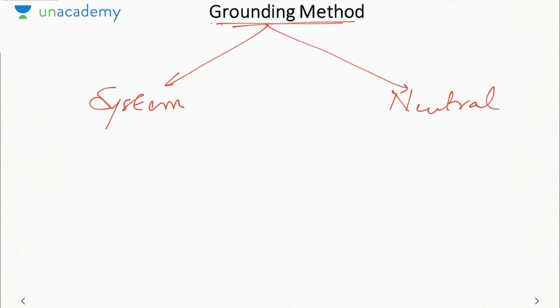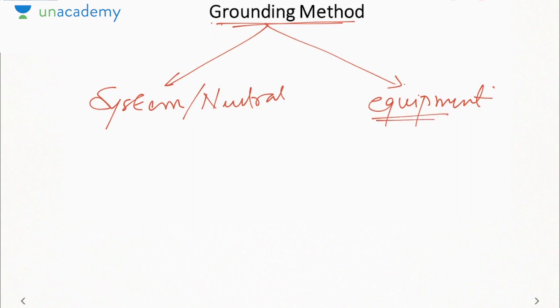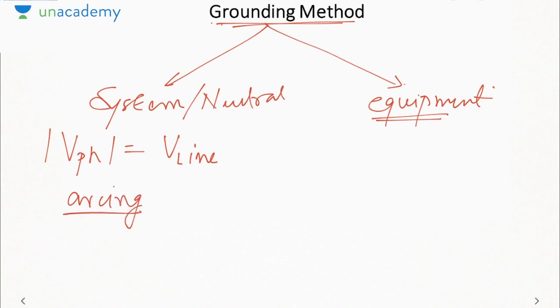Now first of all, what is meant by system grounding? These two terms are actually the same, system or neutral grounding. Next is equipment grounding. So first of all, what is meant by system or the neutral grounding? Neutral grounding means that we will ground the neutral of a system in order to stabilize the system. Otherwise, phase voltage magnitude becomes equal to line voltage due to which there is a formation of arc, which is called an arcing fault. To avoid the formation of arc or arcing faults, we have to connect the neutral to the ground. Otherwise, the system may get damaged. So it is to protect the system from getting damaged due to dangerously high voltages.